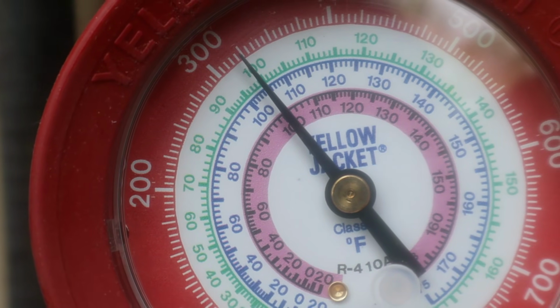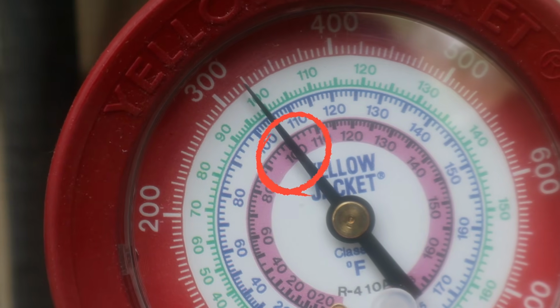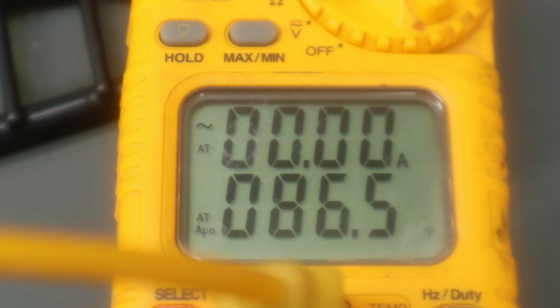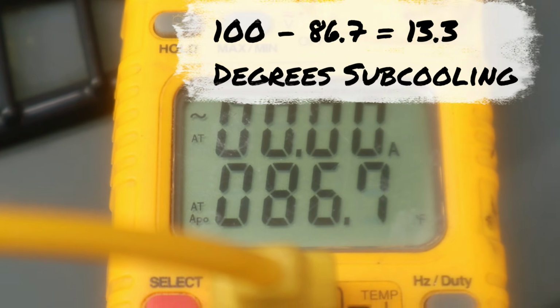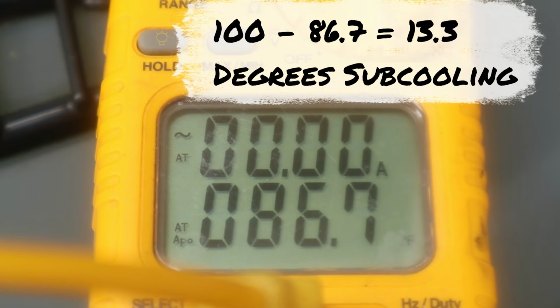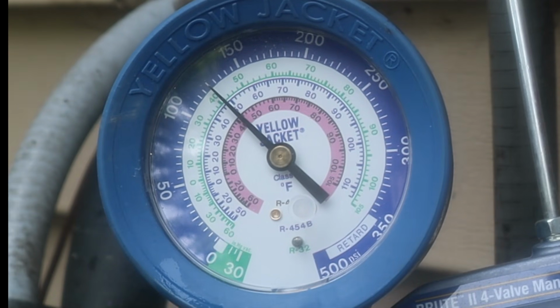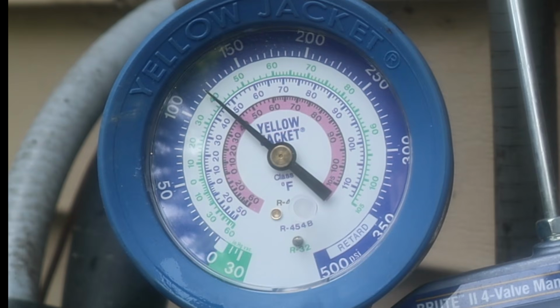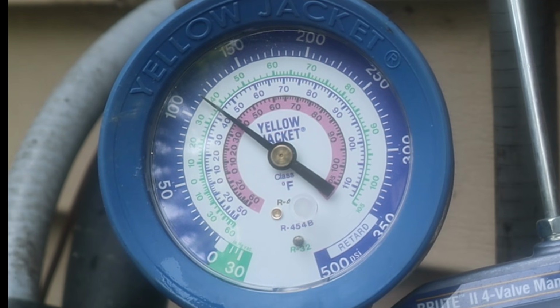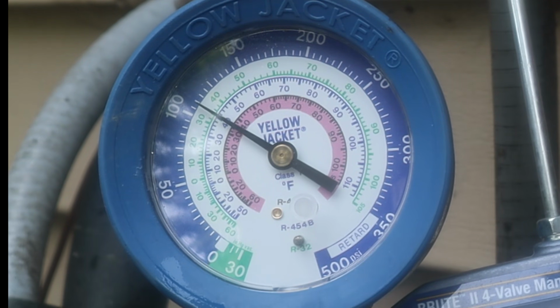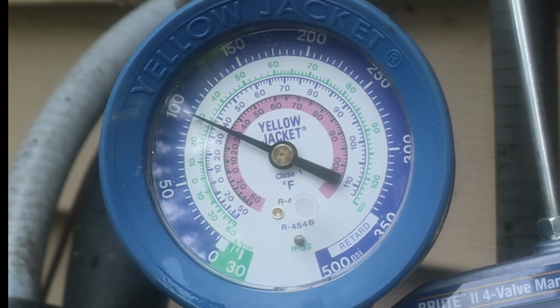Now you can see our saturation temperature is about 100 degrees. And when we look at our liquid line temperature, our subcooling has now increased to 14 degrees. Meanwhile, our suction pressure starts to drop off rapidly, and it just keeps dropping below the normal pressures that we're used to seeing. And eventually it drops off well below the freezing point of water, and now we have problems.